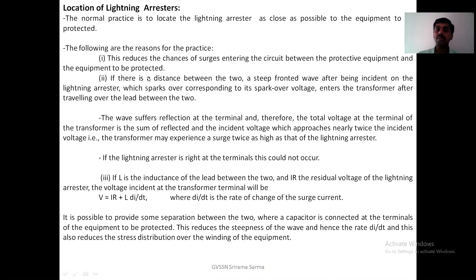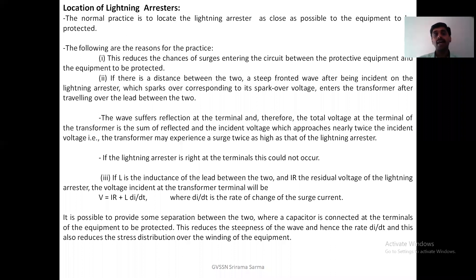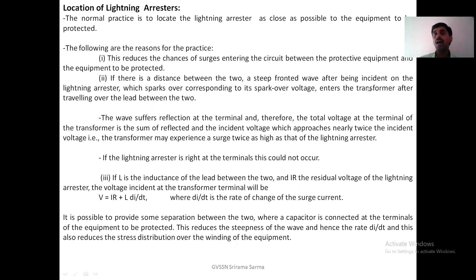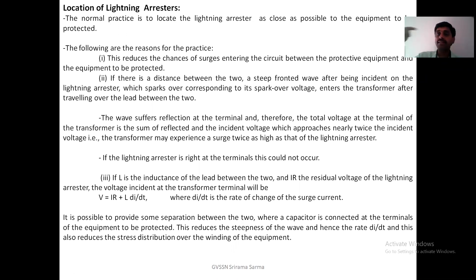That means between the equipment there should not be any chances of surge entering. And if there is a distance between the two — that means between the protective device and the equipment to be protected — then a steep-fronted wave, after being incident on the arrester, once the arrester sparks over corresponding to spark-over voltage, it enters the transformer after traveling over the lead between the two.